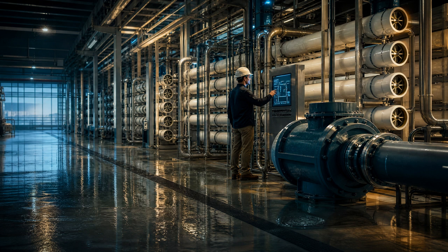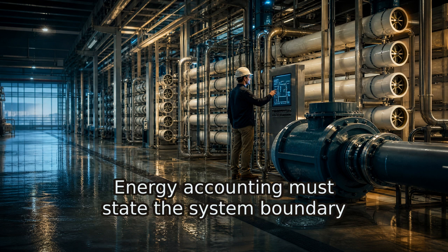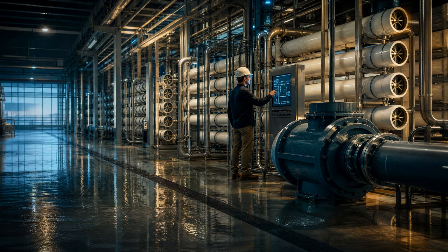It should also distinguish measured performance from an approximate literature range. In a pressure-driven process, the concentrate stream leaves the membrane system with energy associated with its pressure. Energy recovery is the engineering function that seeks to use part of that available hydraulic energy rather than treating it as entirely lost. The principle is straightforward. Reduce the external energy required to provide pressure by transferring or recovering energy from the pressurized concentrate pathway.